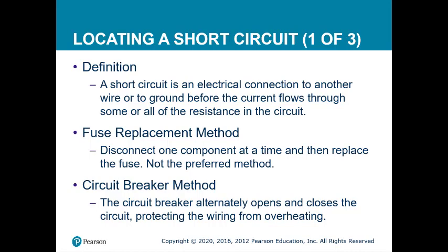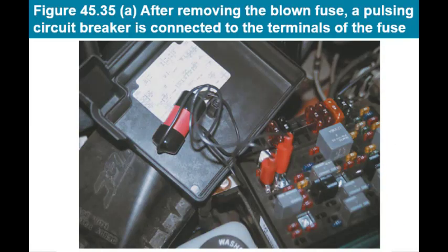There's the fuse replacement method, where you would disconnect one component at a time and then replace the fuse. This is not the preferred method because you go through a lot of fuses. There's the circuit breaker method, where instead of using a fuse, you would use a circuit breaker. So every time the circuit breaker trips, the short circuit is still in play. When the circuit breaker stops tripping, you just found where the short was.